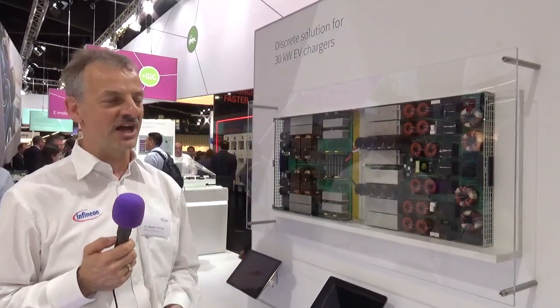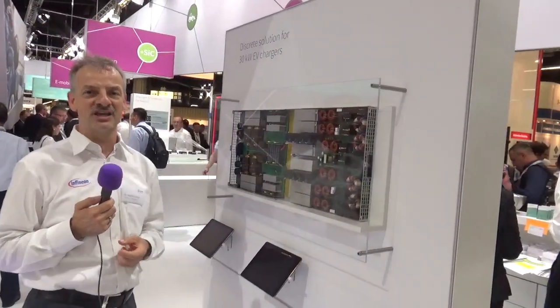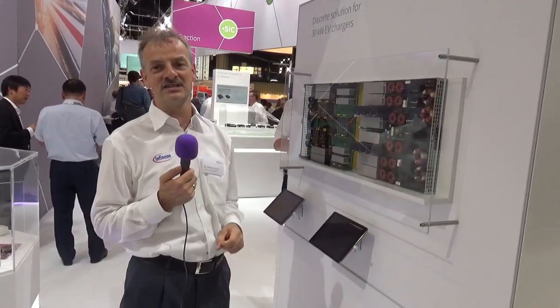This design is very widely spread, especially in Asia and particularly China. It features a lot of semiconductors necessarily mounted to heat sinks, and because the backside of the discrete packages is active, those packages need discrete heat sinks as well. Counting through, you'll find 48 devices on 14 different heat sinks. It's a forced air cooled system, and keep in mind we're trying to go electric to reduce hazardous environments where dirt gathers inside the design. The improvement would be to have all the heat sinks on the outside and all power devices on a common heat sink.